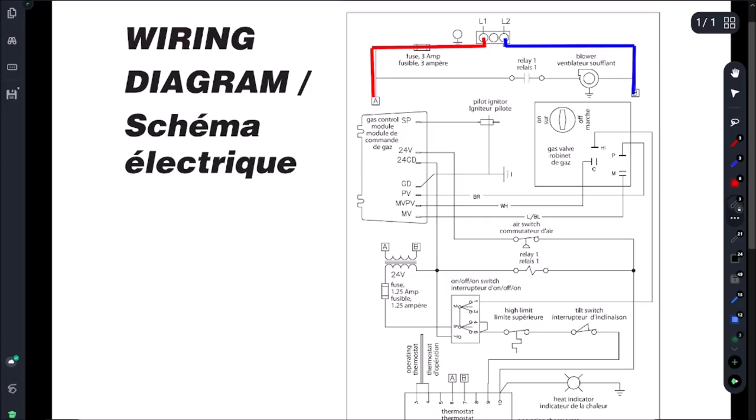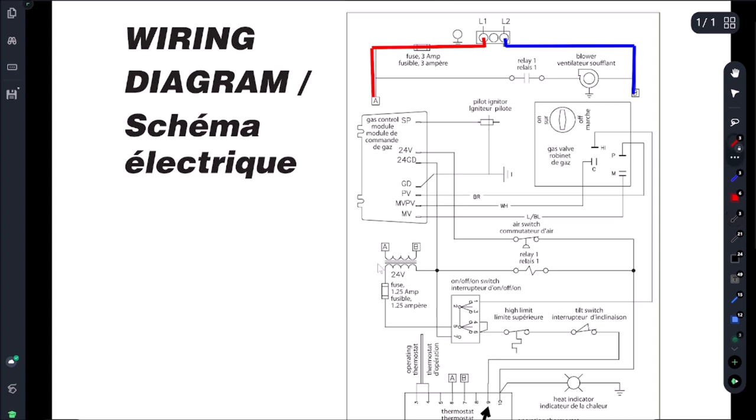Alright so our pin 9 here has no power which is an interesting problem that I've never seen before. So let's just map this out - off pin A we're coming through this fuse. I know this fuse hasn't been blown because the unit will continue to heat as long as we go below let's say 100 degrees - it'll heat, it's just off by 125 degrees.